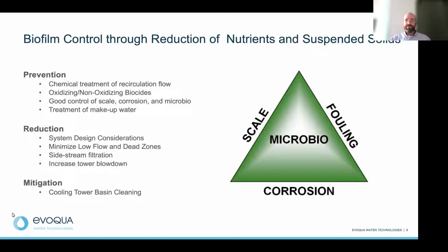what you see on the right-hand side is the cooling water triangle. So this is what you're trying to prevent from happening in your systems. You're trying to prevent scale, you're trying to prevent corrosion, you're trying to prevent fouling, and smack dab in the middle of that triangle is microbio. Why? Because if your bacteria is out of control or you're having issues with it, it can result in scale, fouling, and corrosion. So bacteria is really the key, because if you get that under control, keeping your scale, corrosion, and fouling in check is much, much easier. So microbio is the key.